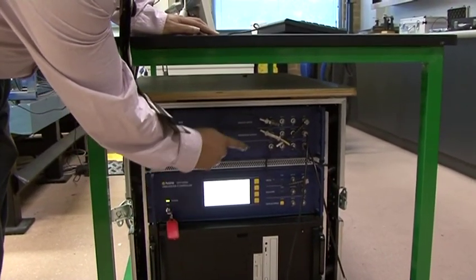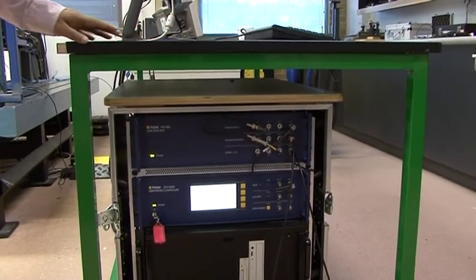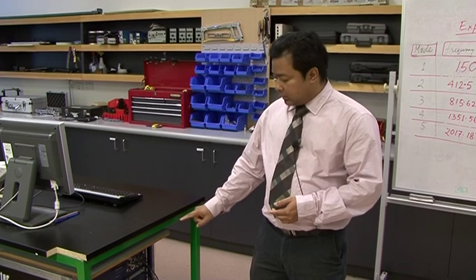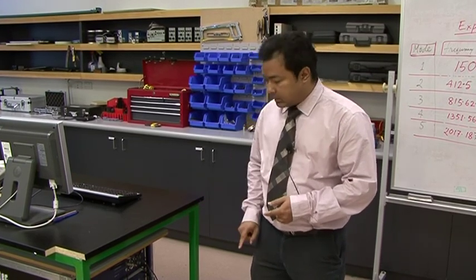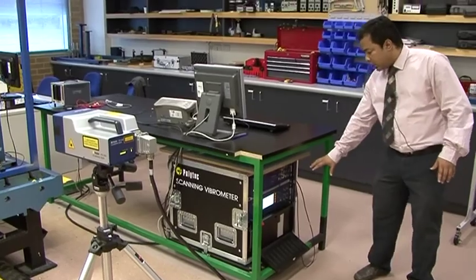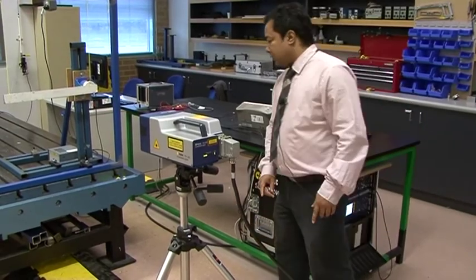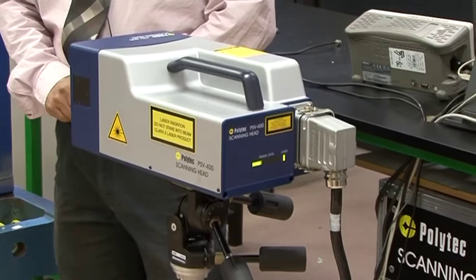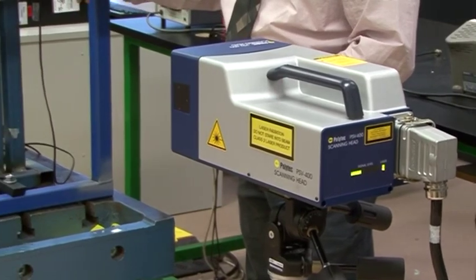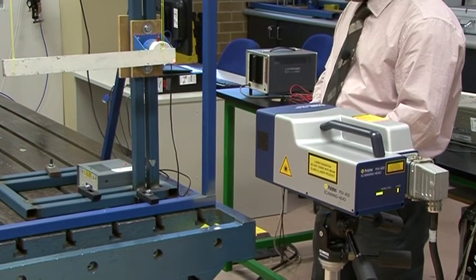The power amplifier input is coming from the signal generator. You can see the signal generator has two racks and this cable is connected going to that amplifier. We need this signal generator to work along with a laser head. The laser head is connected with the software-controlled hardware through a cable. This is the Polytec scanning laser head.